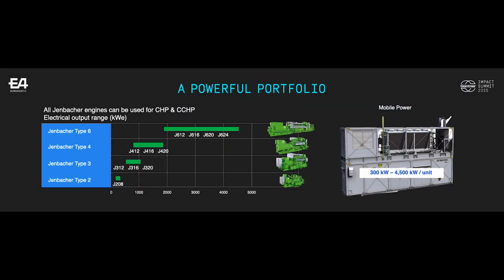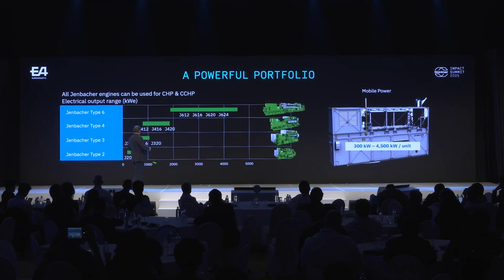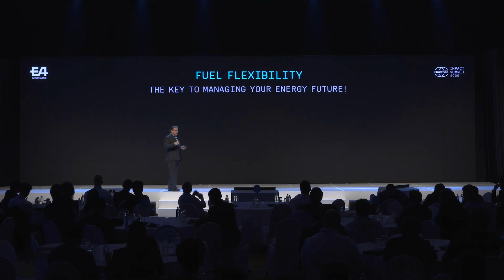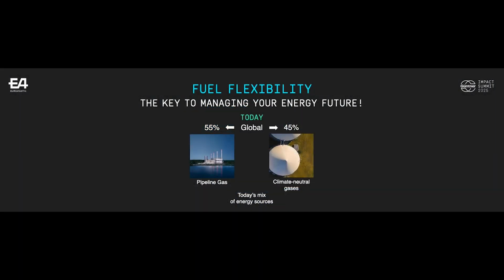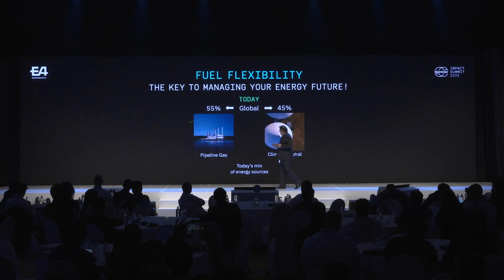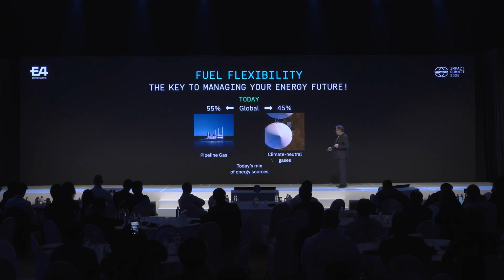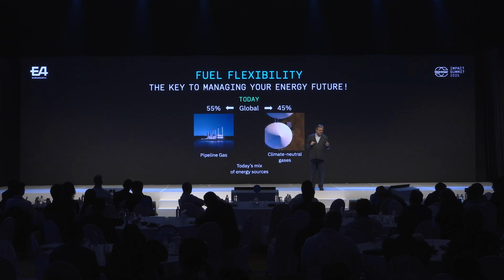So, and now we can go even a step further, as we heard. Jenbacher has a vast portfolio. So we go from 300 kilowatt to 4.5 megawatt. Everything comes also in a box if you need it. But the big advantage of Jenbacher is it can burn more or less any gas which has a good heat rate. Whether it's pipeline gas, it can be mixed with other carbon neutral or carbon free gases. The difference between carbon neutral and carbon free is one is derived out of an organic process, the other one is not producing CO2 when it's burned.